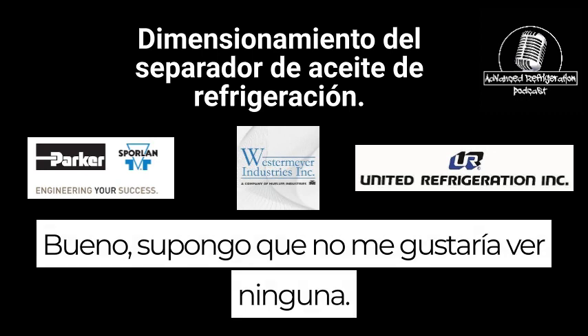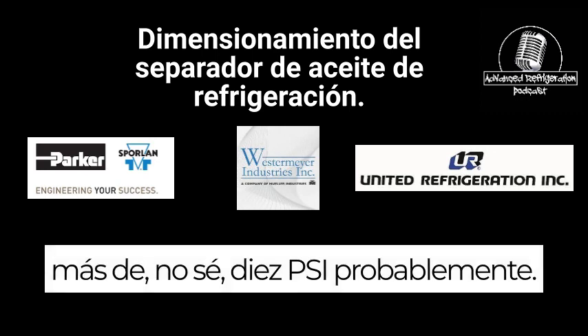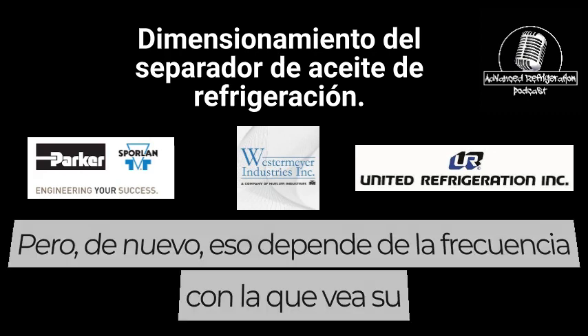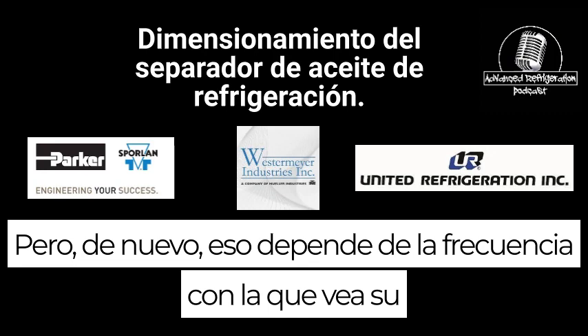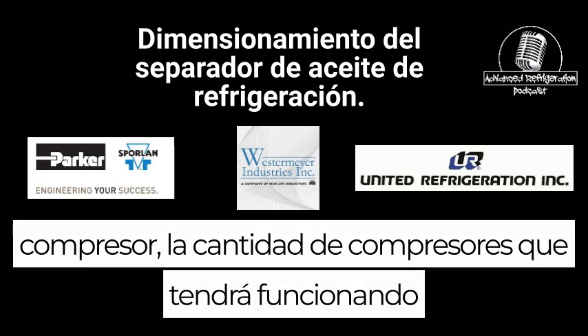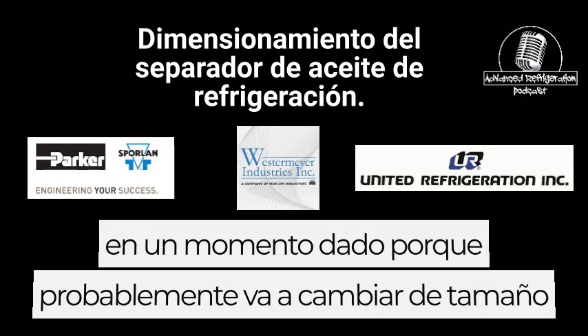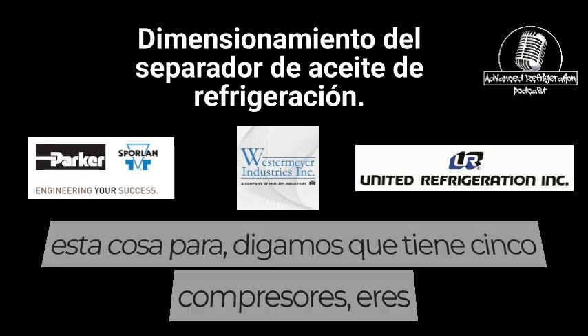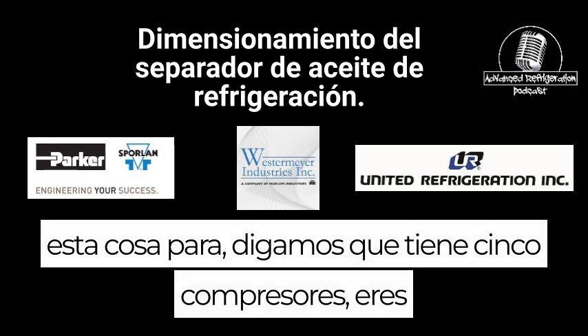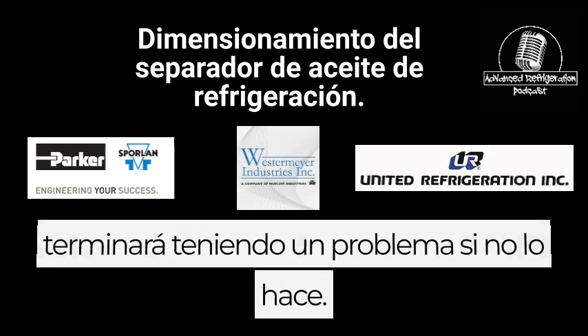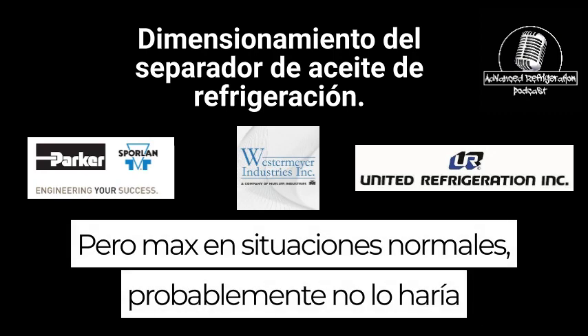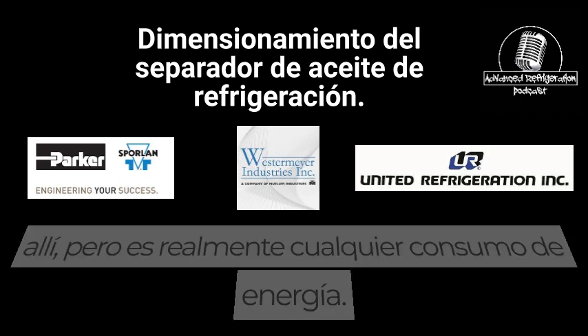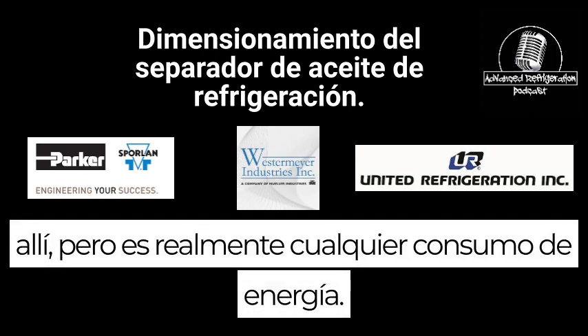Well, I guess I wouldn't want to see any more than, I don't know, 10 psi probably. But again, that's dependent on how often you see your compressor, the number of compressors you're going to have running at any given time, because you're probably going to size this thing for, let's say it's got 5 compressors, you're going to size it for 5 because you're going to end up having a problem if you don't. But max on normal situations, I wouldn't probably want to see anything more than 10 psi on there.